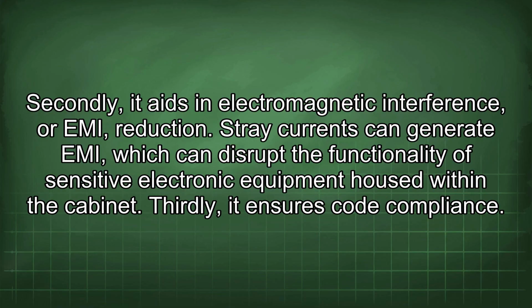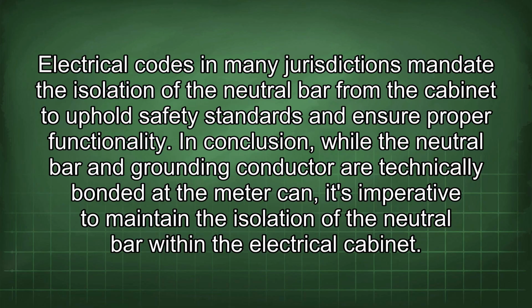Thirdly, it ensures code compliance. Electrical codes in many jurisdictions mandate the isolation of the neutral bar from the cabinet to uphold safety standards and ensure proper functionality.